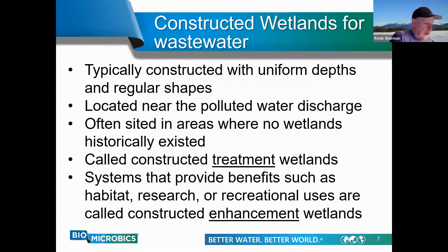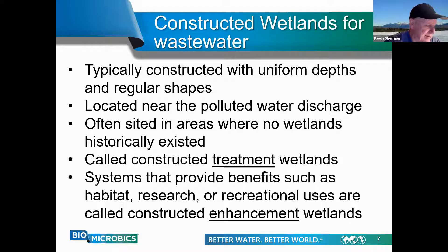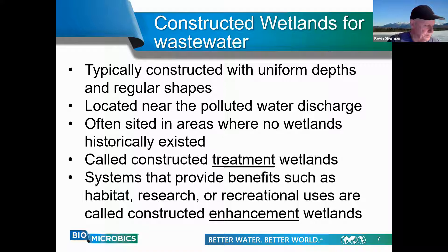Specifically for wastewater treatment, constructed wetlands are built with uniform depths and regular shapes. They should be sited close to the wastewater source to save on conveyance costs. Constructed treatment wetlands can and often are placed in areas that never contained wetlands originally — the wastewater added to the site will allow the wetland ecosystem to thrive. When wetlands are used for additional benefits such as wildlife habitat, research, recreational, or educational uses, they're called enhancement wetlands. Both constructed treatment wetlands and enhancement wetlands have been readily used around the country.